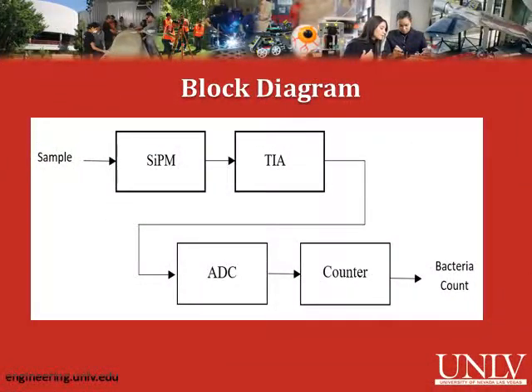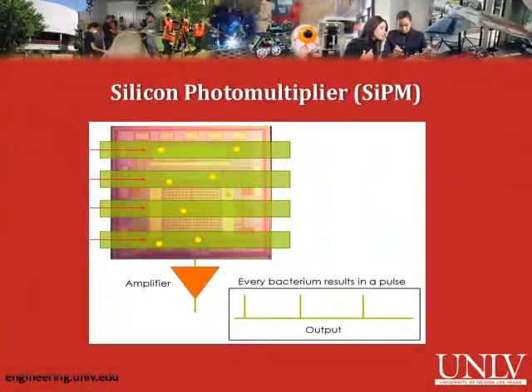This diagram represents our process: the blood sample will flow over the silicon photomultiplier, which will then output a signal that flows through the TIA to the ADC, and finally to the counter which will output the bacteria count. The silicon photomultiplier is a matrix of cells that each absorb photons. When a photon is absorbed by a cell, the silicon photomultiplier outputs a small current pulse in the micro amp range.